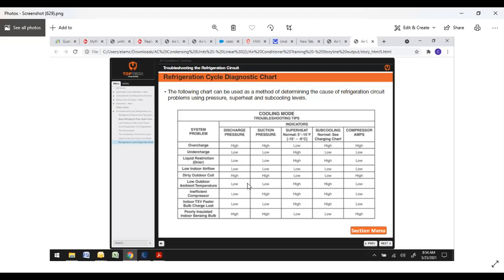Lower outdoor ambient temperature: if you're trying to charge it on too cold of a day, you'll have low discharge and low suction. You will have high superheat, high subcooling, and low amperage because you're not really working that compressor too hard. If you have an inefficient compressor, this goes back more to the reciprocating compressors. If you have a damaged scroll, it's usually obvious. It'll be metallic and clangy sounding, and sometimes it sounds downright violent. But if you had an inefficient compressor, you could have a low discharge pressure and a high suction pressure. You could have a super high superheat because it's not cooling, super high subcooling, and low amperage.